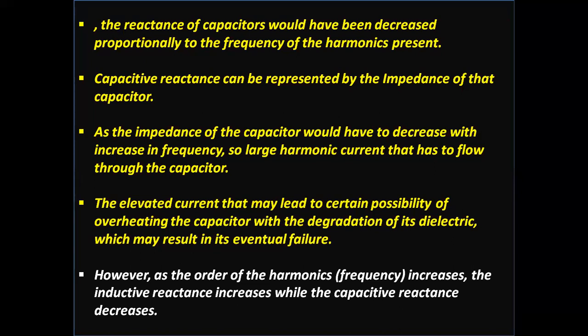As the impedance of the capacitor decreases with an increase in frequency, a large harmonic current flows through the capacitor. The elevated current may lead to overheating of the capacitor with degradation of its dielectric, which may result in its eventual failure. However, as the order of the harmonic frequency increases, the inductive reactance increases while the capacitive reactance decreases.